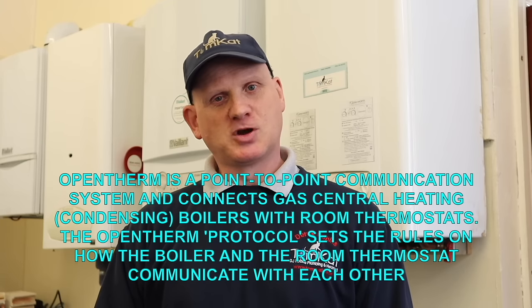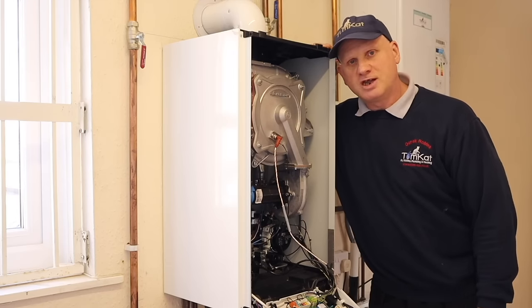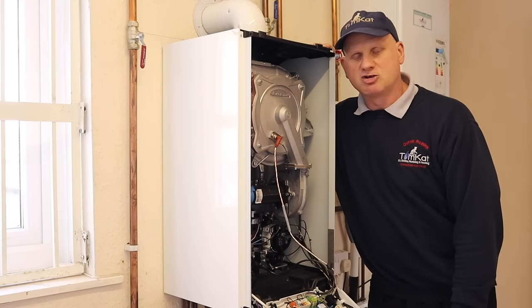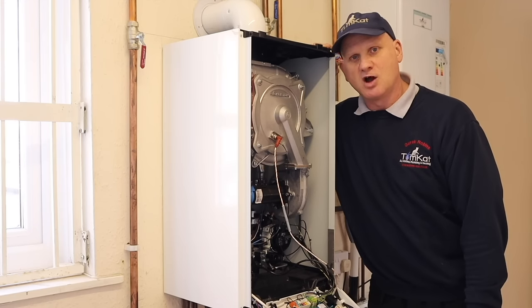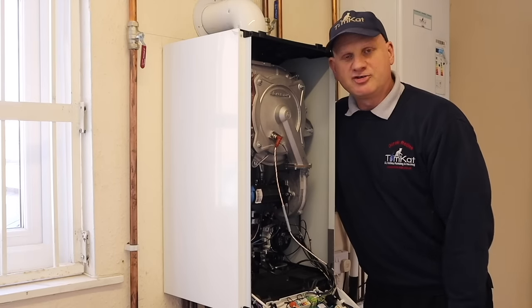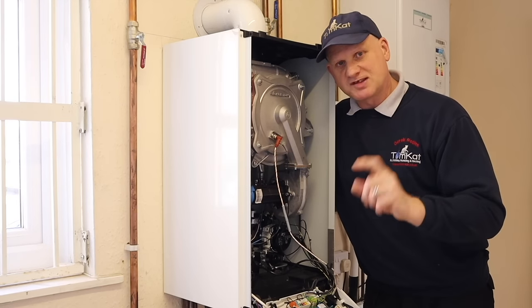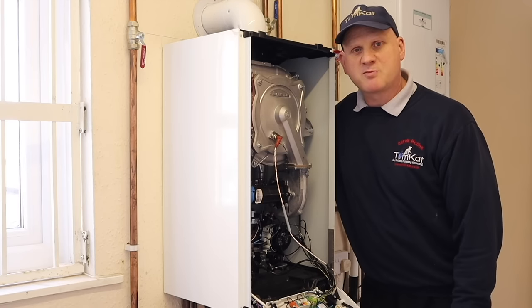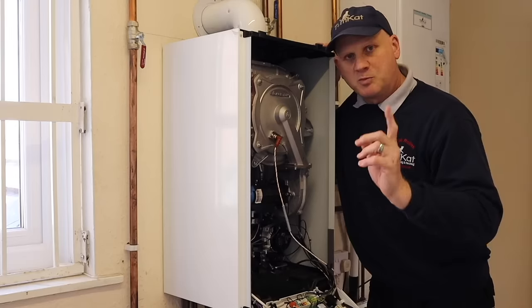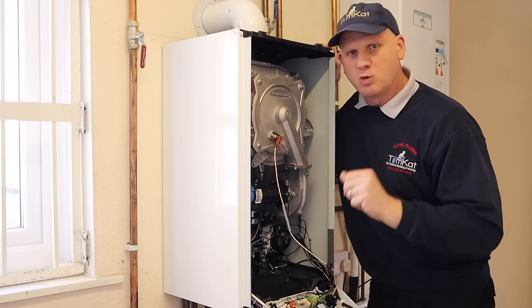The language these boilers speak is called OpenTherm, or some call it eBUS, and other manufacturers have other names for this. So make sure when you're installing or purchasing a new boiler, you've got controls which speak OpenTherm or eBUS or mBUS, or whatever other language the boiler is speaking to the controls. All engineers should know that the introduction of smart controls should increase the efficiency of the boiler they've just installed. The introduction of these smart controls has driven sales in this sector with high expectations of energy savings. But once again, things might not be what they should be.